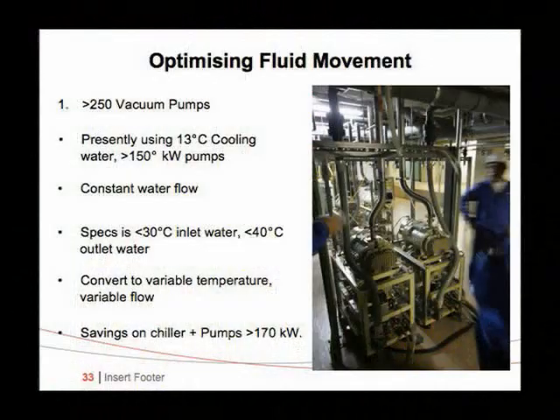So you can actually vary the flow through the pumps when it's not working. So we can actually go to variable temperature and variable flow. You don't need 13, which is a load on the chiller and more chill water piping and plate heat exchangers. And so if we were to redo a quick estimate, it's 170 kilowatt a fab. Five fabs. You know.